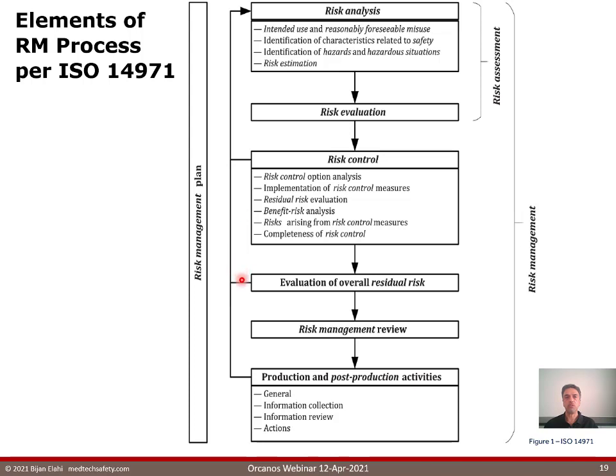And then we move to the evaluation of overall residual risk. A medical device presents a number of individual risks, but put together that becomes the overall risk of the medical device. It is what matters to patients, not individual risks, but the overall residual risks. So to arrive at this box here, we need to know what the overall residual risk of the medical device is, and then evaluate that. The next activity here is the risk management review, which has a number of activities. The output of this step is the risk management report. Once the device is approved and is released, then we go into production and post-production activities, which has a number of activities. Generally speaking, that's about information collection, about how the device is performing, reviewing that information and taking appropriate actions due to the information that we have collected.